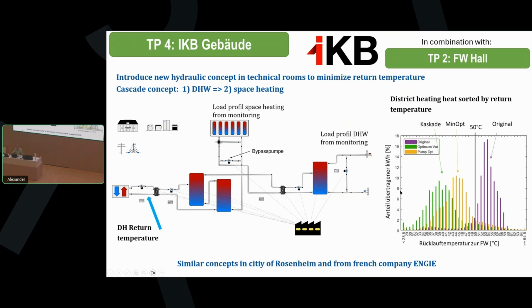then you can get this distribution of the yellow bars. And if you make a cascade concept, where some first systems are installed in Germany, in Rosenheim, Munich, and also in France, the principle is that you have the buffer storage and you first make the domestic hot water. You don't care about the high return temperatures because this return temperature is then used by the mixing valve for the space heating system. And in the end, you get back the return temperature of the space heating system, which is typically much lower. And if you make a system like that, then you get the result, the green bars here. You can see we are in total more than 10 degrees lower on average in temperature. So that's something we are going to test.